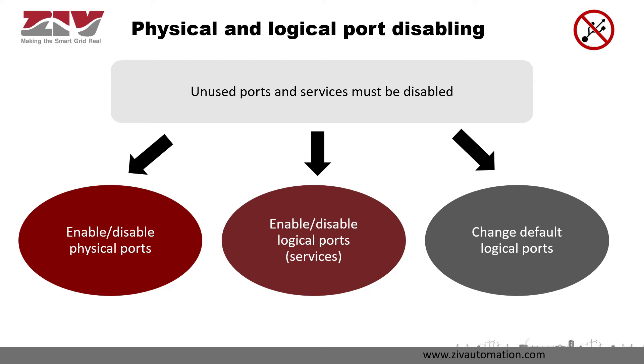The IED also offers the possibility of enabling and disabling logical ports, also known as services — for example, FTP or SFTP, HTTP or HTTPS, Telnet or SSH, MMS for IEC 61850, SNTP, Syslog, other protocols like DNP3 or Modbus, proprietary protocols like Procome, and protocols for remote authentication like LDAP or RADIUS.